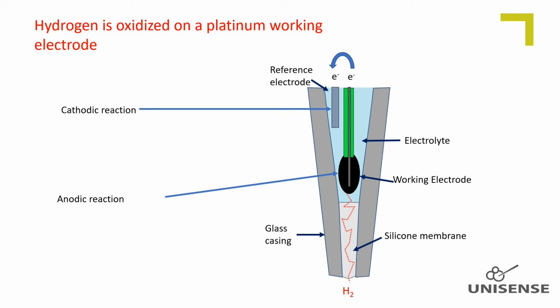We do not give detailed information about the electrolyte composition and electrochemical reactions because it is a proprietary recipe which is not protected by patents. The reference is placed 10 to 15 centimeters away from the working electrode, but for sake of illustrating the principles, it is included in the schematic drawing of the tip. The current generated is proportional to the concentration of hydrogen outside the tip membrane, and as the current is very small, in the picoamp range, a high quality amperemeter is necessary for amplifying such tiny current. The electrolyte solution ensures electrical connection between the electrodes and ensures charge balance.